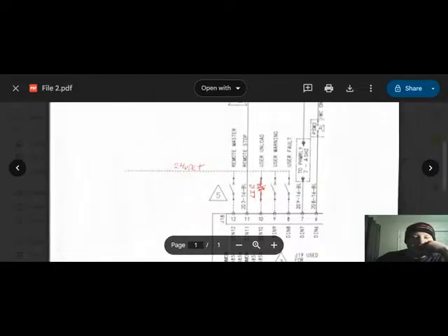The way we would do this is we would take this 24 volt DC signal right here that's being generated by the IO module. We would run this through our relay that's been wired up and given to us by the plant electrician. This relay is going to change states based on whether the lights are on or off. And we want to come through the normally closed contact of this relay to give this signal right here to input 10.